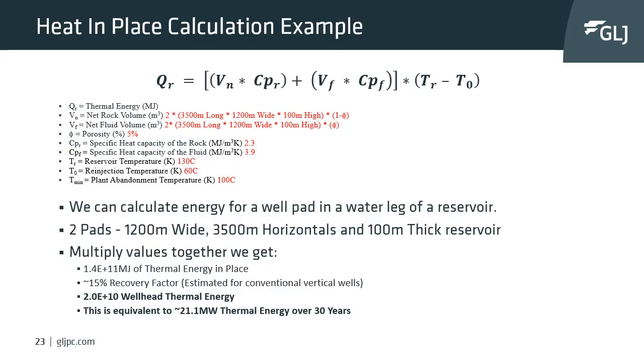We'll now do an example heat in place calculation using EGS horizontal wells, since horizontal wells produce much more than vertical wells. For an example of two pads — 1,200 meters wide, 3,500 meter horizontal sections, 100 meter thick reservoir — we calculate the net rock volume and net fluid volume using porosity, with generic values for specific heat capacities. At a predicted reservoir temperature of 130°C, re-injecting at 60°C, and a minimum plant temperature of 100°C, calculating over 30 years gives about 21 megawatts of thermal energy using a 15% recovery factor based on conventional vertical wells.